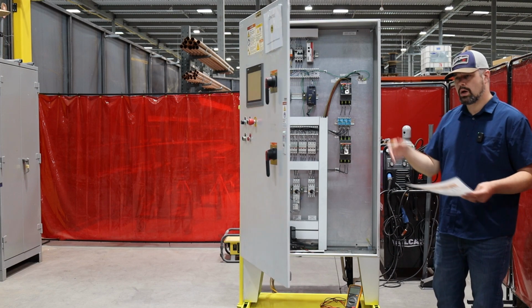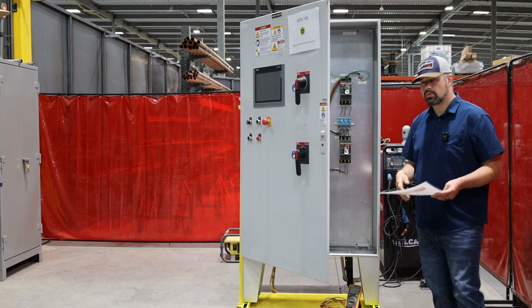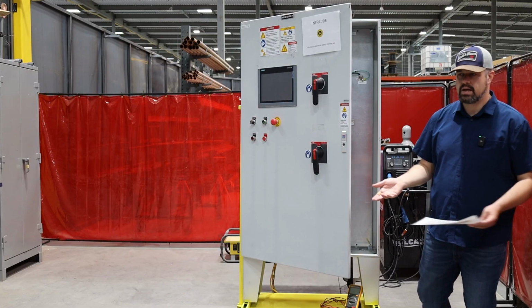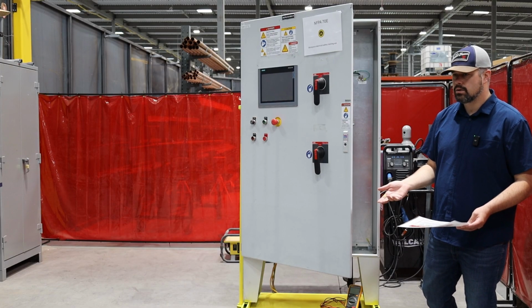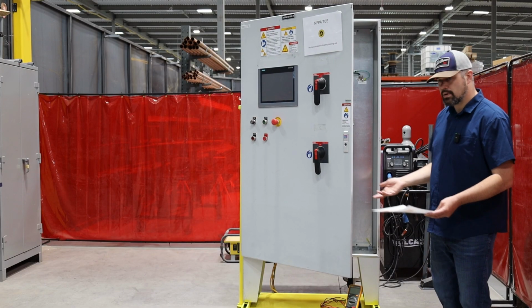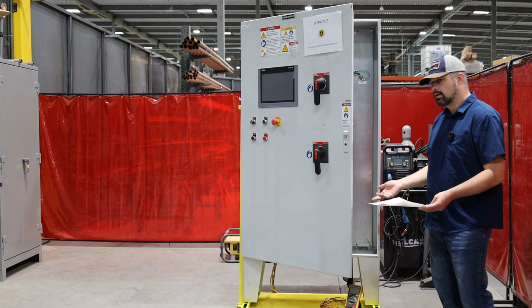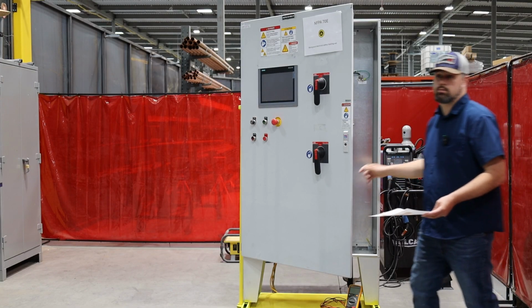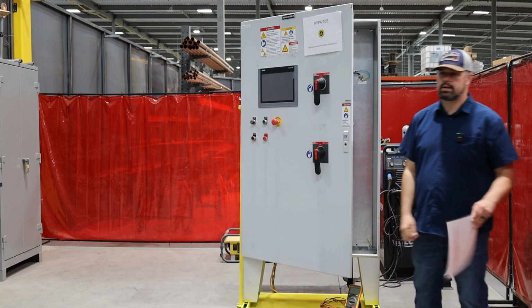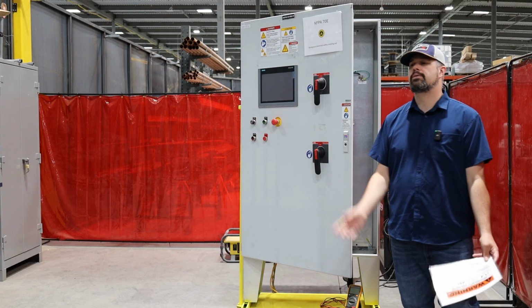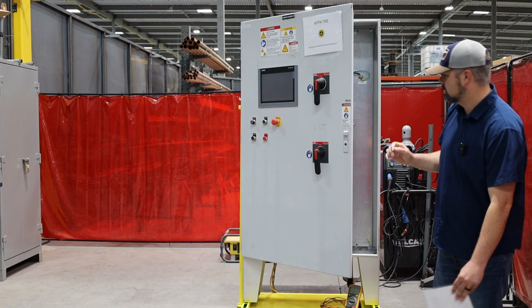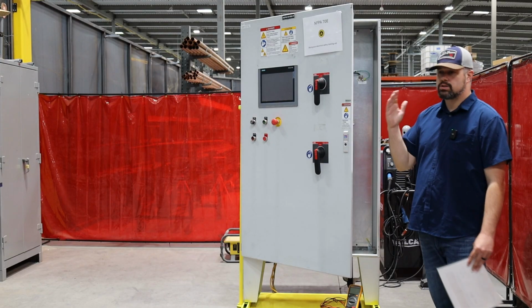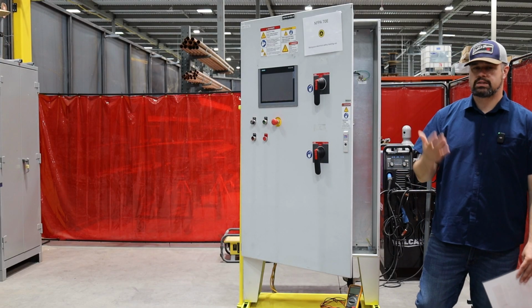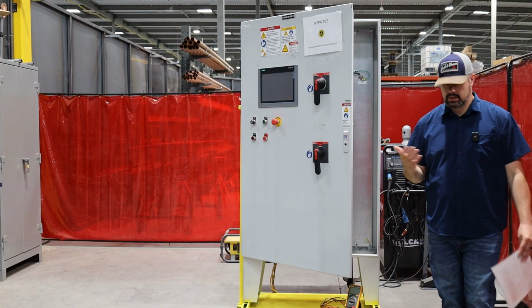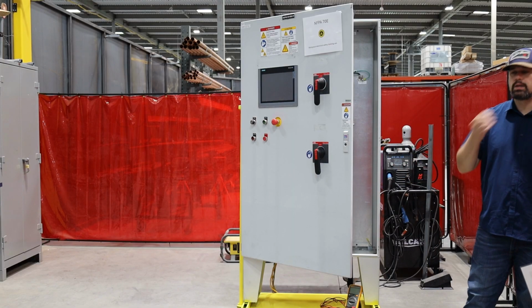So now, as level 1 qualified electrical workers who have successfully gone through the NFPA 70E training plan, you are authorized and cleared to do all those things. You are not okay to just reach in and reset a breaker. That's definitely not best practice. The breaker tripped for a reason. We need to figure out why. So in this scenario, you're going to escalate that to the maintenance supervisor, and they're going to start that process to see what's going on. Why is the breaker tripping? Who else do we need to get involved here?